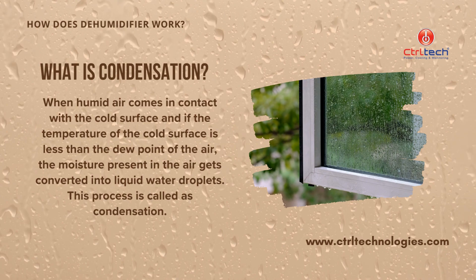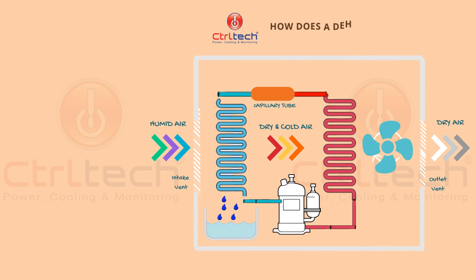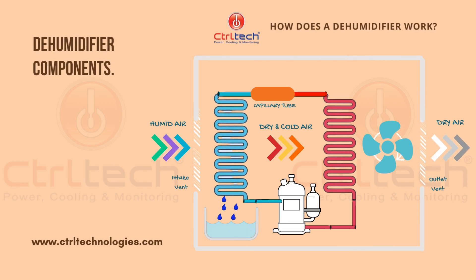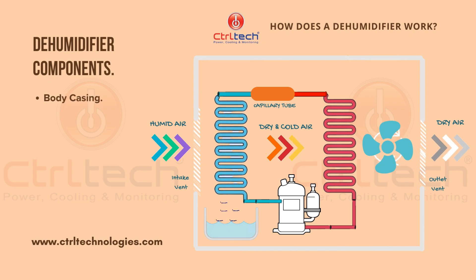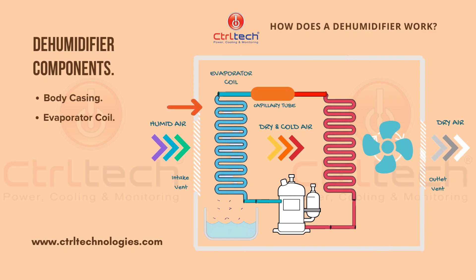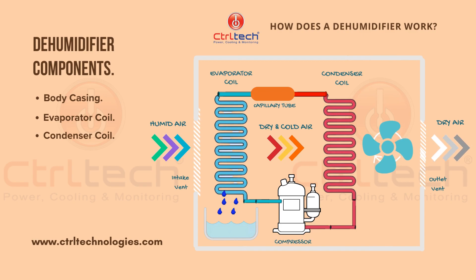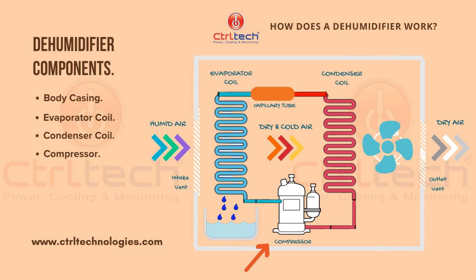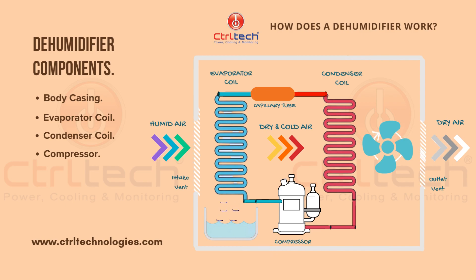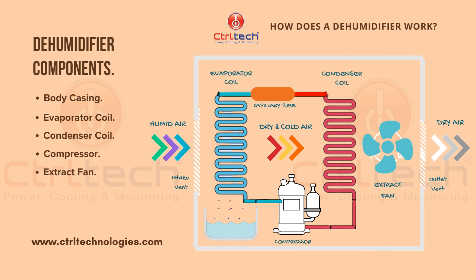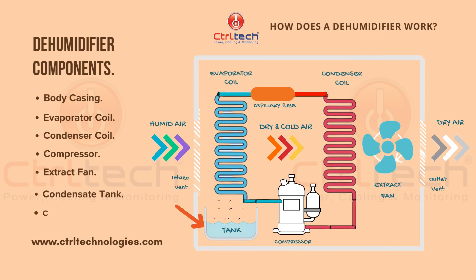A condensation dehumidifier uses the same principle to remove humidity from the air. To understand the working of a compressor dehumidifier, you need to understand its components. It has a body casing which houses all the components. It has an evaporator coil where the actual condensation happens. It has a condenser coil which is used to reheat dry cold air. It has a compressor — the heart of the refrigerant cycle — which increases the pressure of the refrigerant gas. The refrigerant gas enters the compressor at low pressure and low temperature and leaves at high pressure and high temperature. It also has an extract fan to pull humid air into the dehumidifier, and a condensate tank to collect the condensate water.